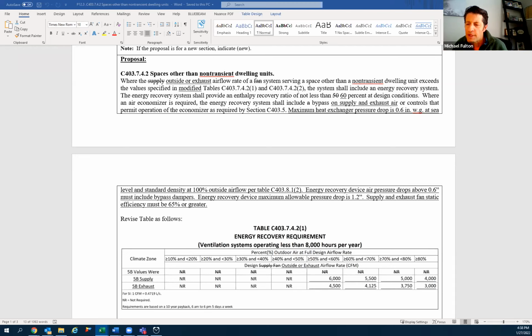To Mark's point earlier, you could have a really poor bypass damper, so limiting to 0.6 in bypass is a good idea, but the concept is, designed on a -5 degree day, if you had 1.2, you're saving a lot of energy, but in the bulk of the hours, so 45, 35 degrees, you'd be allowing bypass past the wheel or plate heat exchanger to get your fan energy down.